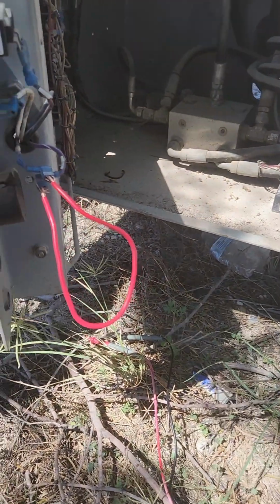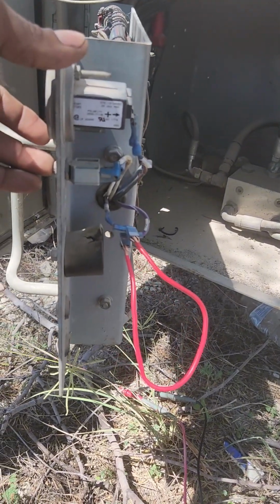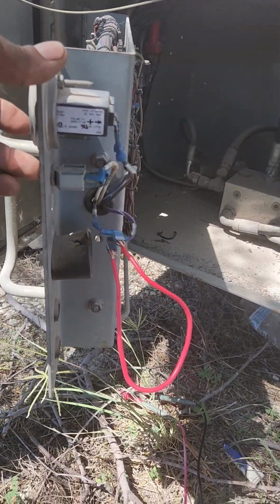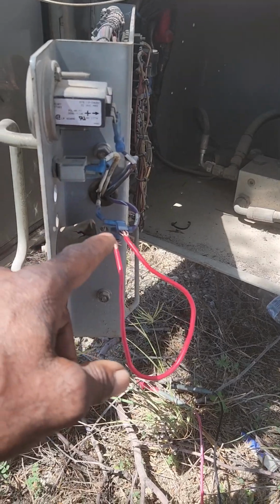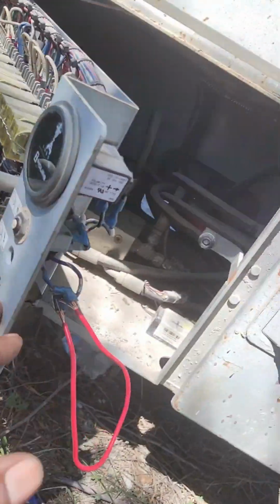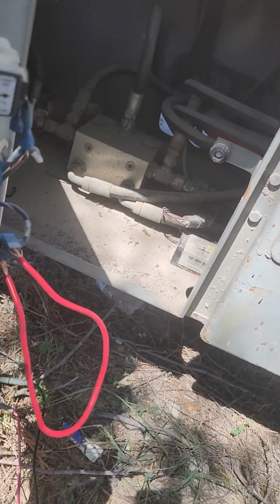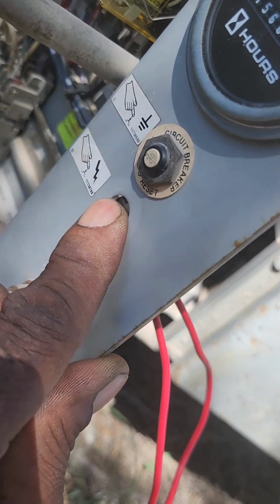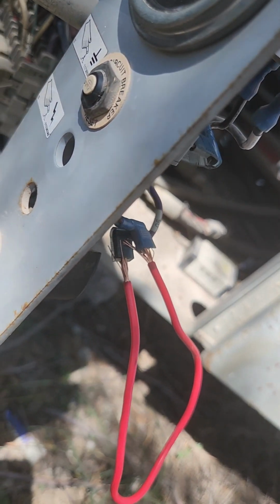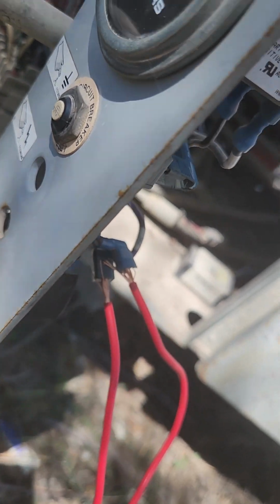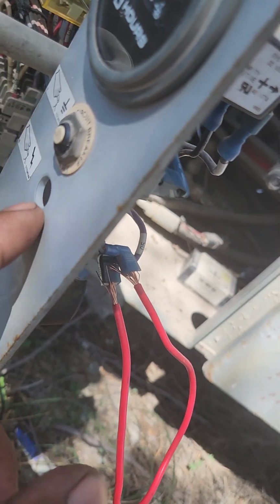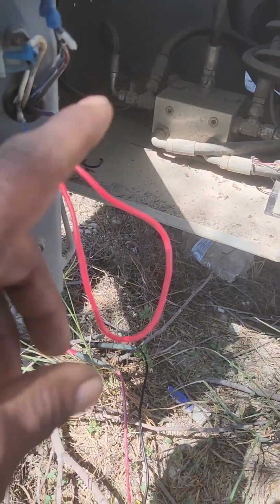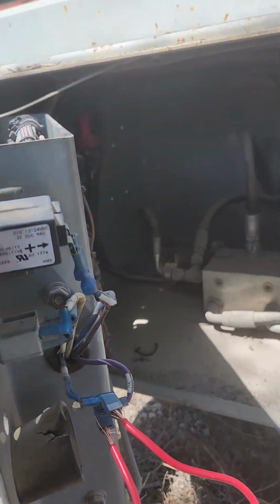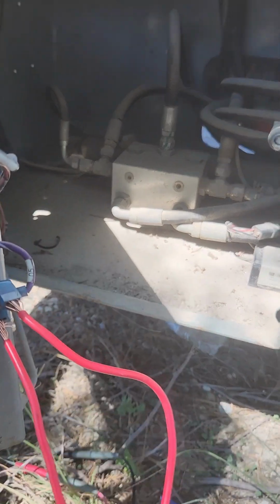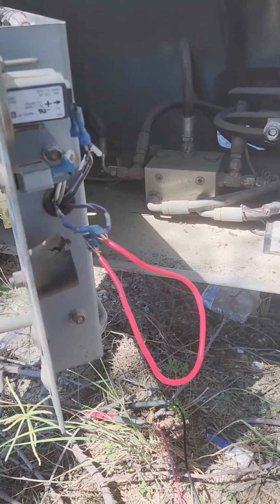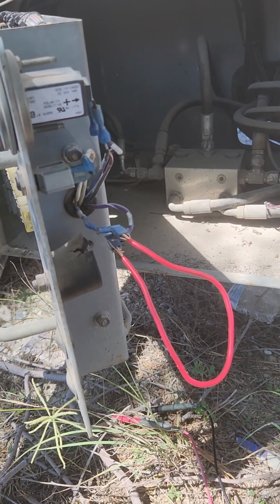So they have a circuit breaker, so if it cranks too high of amps, meaning the starter's bad, they just reset the breaker. But since it broke, it blew, and they put a fuse in instead. The fuse blew but didn't reset because it's not a circuit breaker. If this one here blows, it's supposed to have a circuit breaker here, so when it has too many amps, it just pops out. If the starter is hard to start or takes too long, it pops the circuit breaker out, and when you let it cool off you push it back in. Since they took out the circuit breaker and put in that fuse, and fuses don't reset themselves, they just blow. So we need to get a circuit breaker and put it in there, and it should work fine.